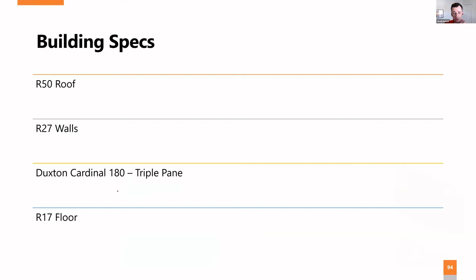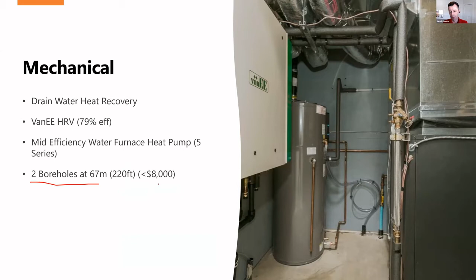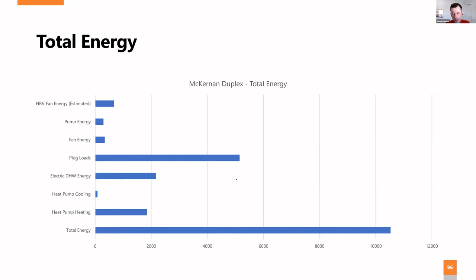And that was actually part of the reason why we improved the envelope, is we wanted to keep the drilling to a minimum just for the footprint. So you only needed 2 boreholes per side, so less than $8,000 for the drilling costs. And we used a mid-efficiency heat pump. Our energy usage was just over 10,000 kilowatt hours. And based on the roof space we had, we could easily reach net zero.